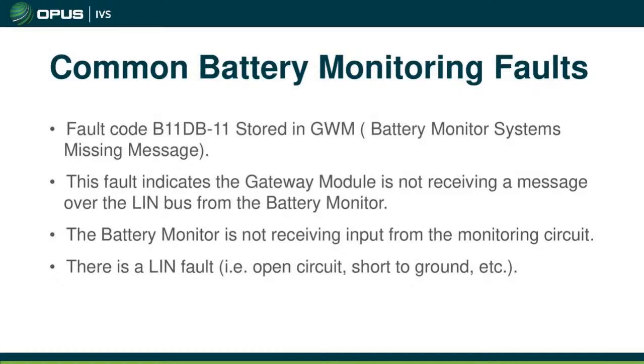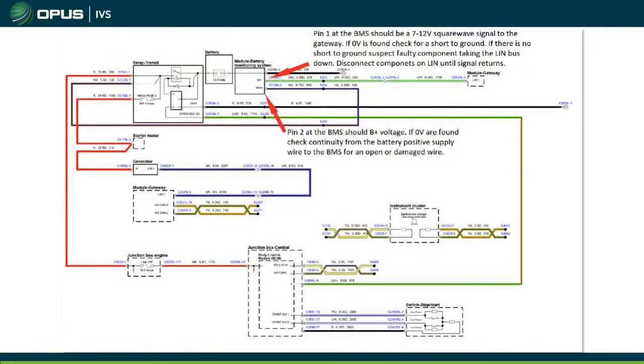So always keep that in mind. If you get that fault there in the gateway module and it is a hard fault, make sure you start at that BMS. Check the battery here. All right, you can see we have the BMS right there at the top. So you got two lines going in and out. You got your monitor line coming from the B plus. Ensure that you have B plus present there, not a volt off of B plus, not 2 volts off of B plus, but whatever you measure at the battery, you should find that equal value on the monitor circuit.